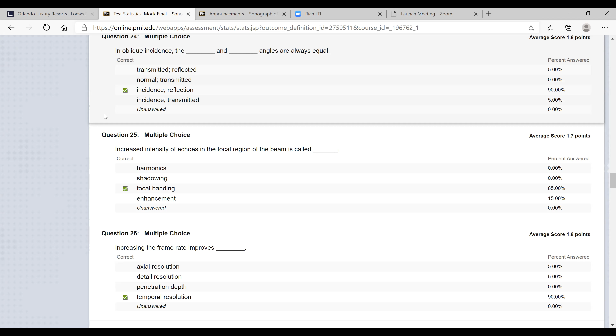Increased intensity of echoes in the focal region of the beam is called, oh yeah, 85% got that, focal banding. The beam has narrowed down to its thinnest point in the focal region, specifically at the focal point. That's going to increase intensity because your beam per square centimeter has gone down. So the strength of that echo is going to go up right at that specific point. And to fix that, you just use your TGCs.